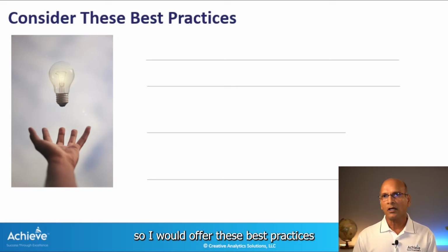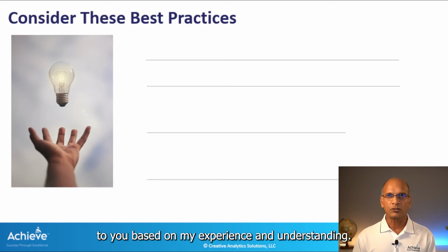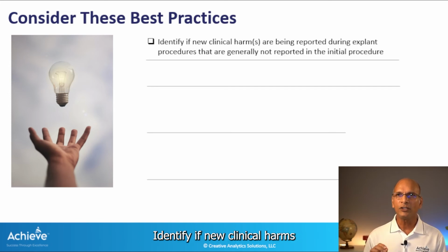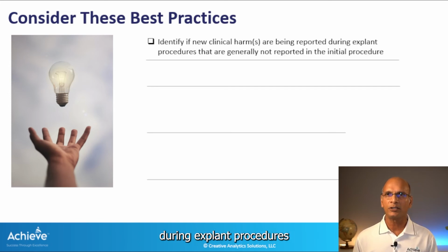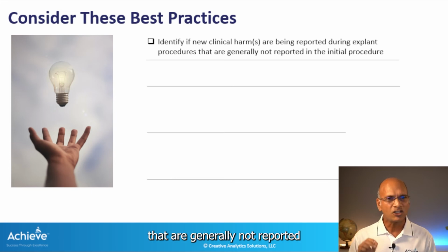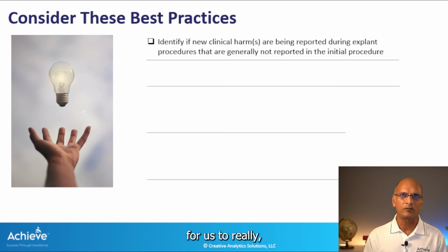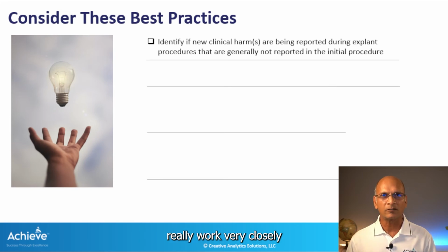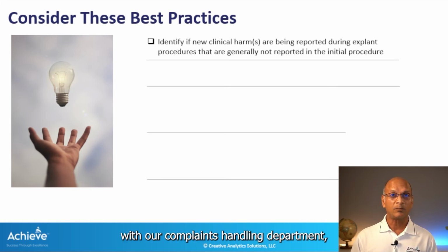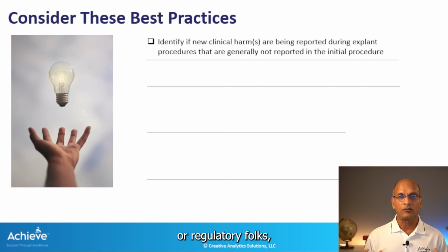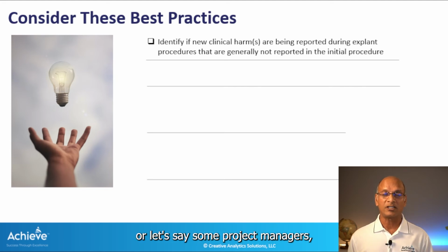So I would offer these best practices to you based on my experience and understanding. Identify if new clinical harms are being reported during explant procedures that are generally not reported in the initial procedure. And this is why it's very important for us to really work very closely with our complaints handling department, with our clinicians.